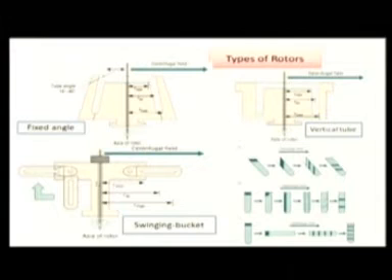And the other model which we widely use in clinical practice and research purposes is the swinging bucket model, which you can see on the bottom side of the slide towards your left. So here you can see this is called the swinging bucket model. Here I would like to explain a few small important things. In this swinging bucket model, the tube is in the normal position when the centrifuge is stable.